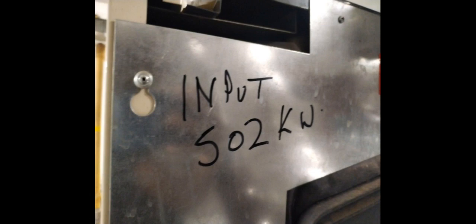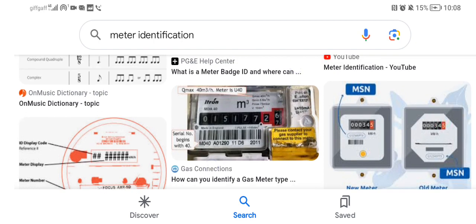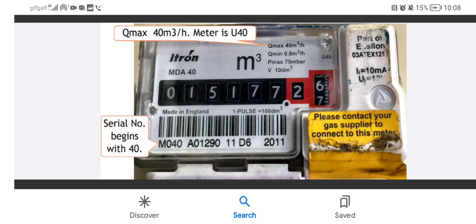Let me know how you work out the same calculation. On the back of the boiler it has 502 kilowatts written on it, but I couldn't find any data badge on the actual boiler itself. Also, a quick thing I'd like to show you — there's been a query on one of my videos about tightness testing, where one or two engineers believe the meter volume is this number shown here with the 'V'. If you want to know the volume of the meter, always look at where the barcode and serial number are.